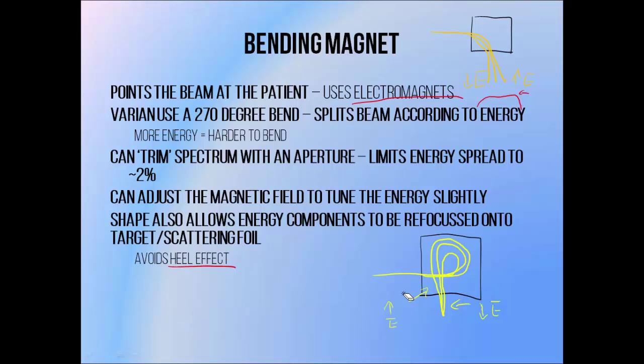Because the electron beam is separated into different energy components we can pass it through an aperture which allows us to select for very specific energies — ones that are too low energy will hit one side of the aperture and won't make it through, and ones that are too high energy will hit the other side. This allows us to limit the spread of energy within our beam to approximately 2%. Thanks to this aperture we can also adjust the strength of the magnetic field slightly in order to select for slightly different energies and fine tune the beam energy if we wish.